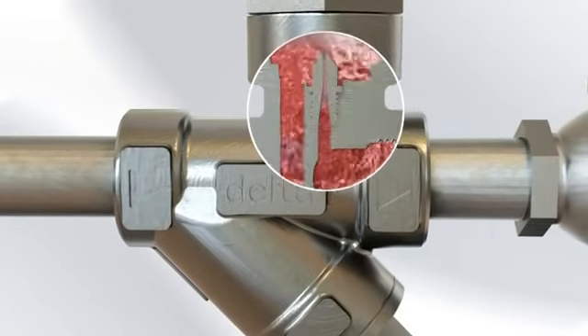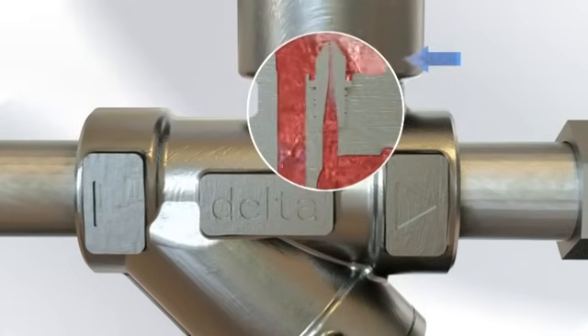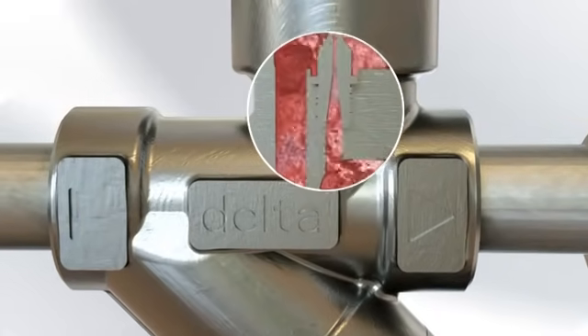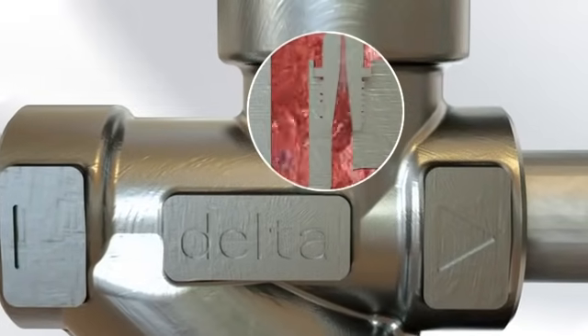so too does the percentage of flash steam being created at the mouth of the Venturi in the Delta Steam Trap, which in turn allows the back pressure at the Venturi to vary accordingly.